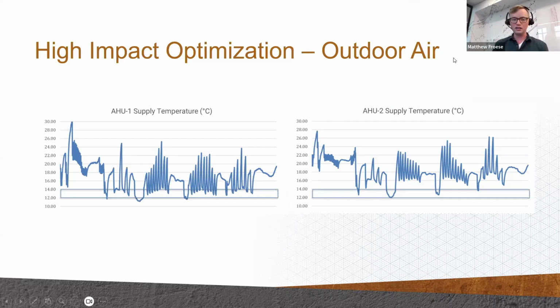So these should be identical, but our supply on the one side there is hitting our performance range when it's being called on. You can see on the left side, we're getting into that 12 to 14 degree supply range for cooling. But air handler 2 on the right, basically never getting there unless it's overnight and it happens to be off and it's just cold outside. That's what that temperature sensor is saying.